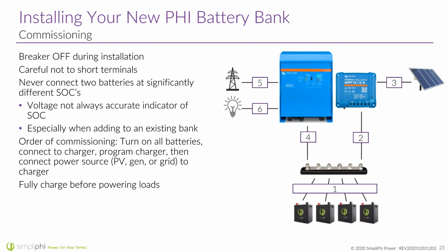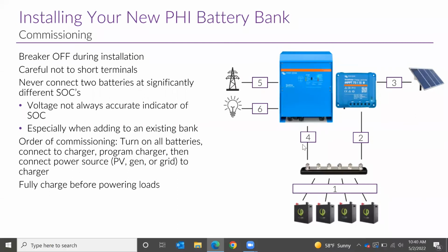As far as order of commissioning, be careful not to short the terminals. Turn on all the batteries first, then the disconnect to the charging source, then once that's connected, connect to the PV array. As far as inverters, if you don't have a charge controller, do the same thing: batteries on first, then the DC disconnect for the inverter, then the charging source for the inverter, and finally, after they're charged, turn on the loads.